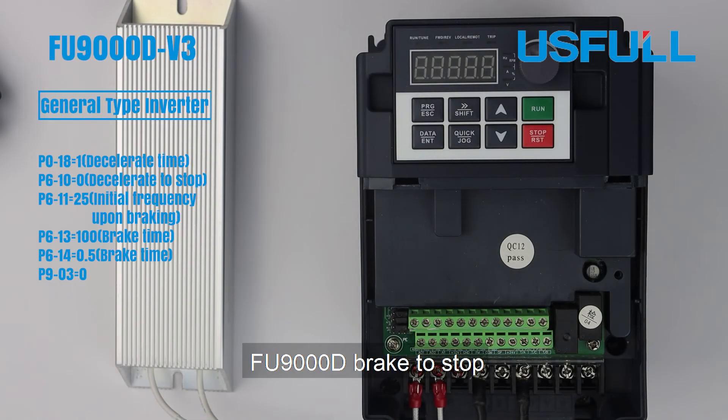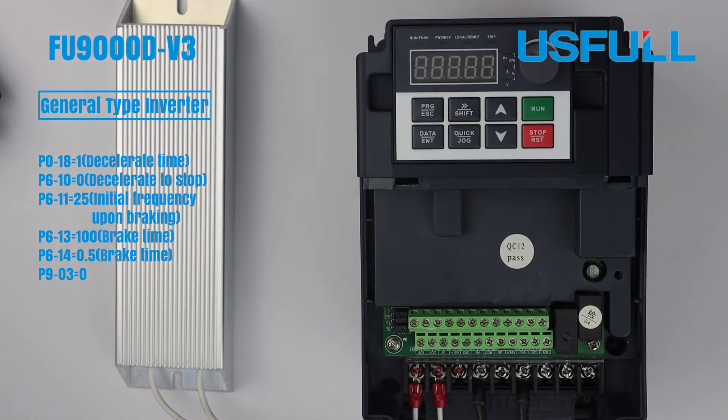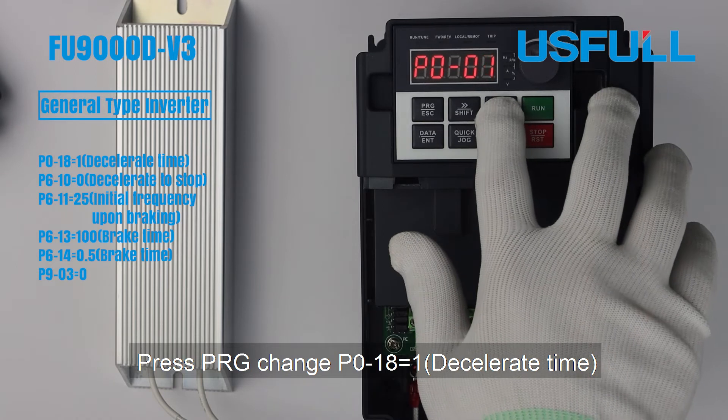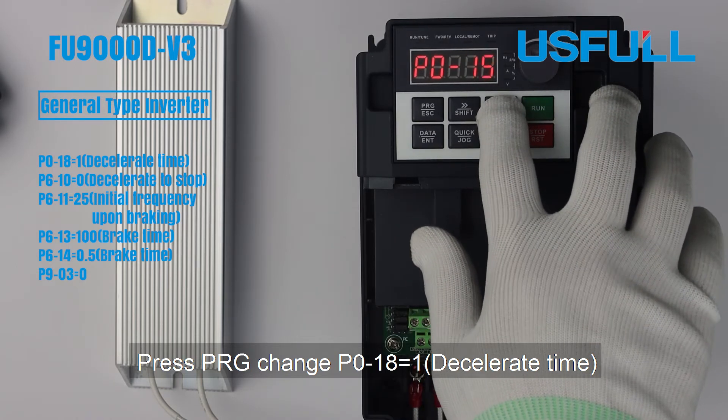USFULL FU9000D, brake to stop. Press PRG, change P018 to 1, decelerate time.